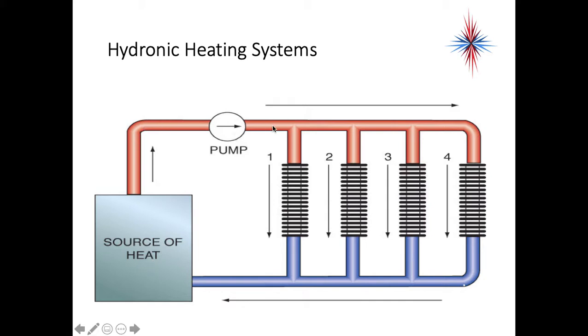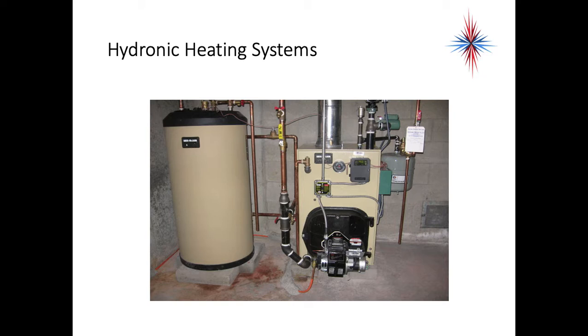We have a circulator pump and we have zones. This is a parallel system — sometimes you have zone radiator after radiator after radiator. This is an example of one such hydronic heating system. You'll see the circulator on the right-hand side, an expansion tank, controls, an oil burner, and an indirect hot water tank. The more valves installed, the better, because it allows you to isolate parts of the system.